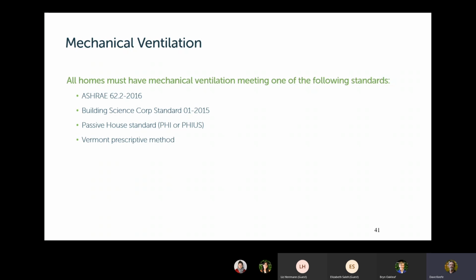Up until 2015, we only had one option for that, and that was the Vermont prescriptive method. And I'm going to explain to you what that one is. That's the simplest one. Starting in 2015, we were allowed to use ASHRAE 62 instead. And with the new code, the 2020 code that kicks in in September, two more options have been added. So you can now choose from these four standards.